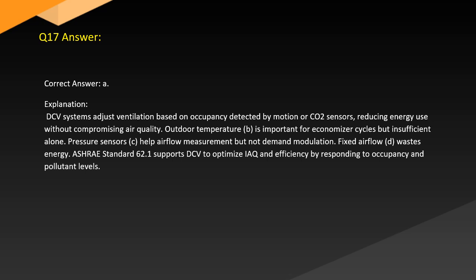Answer. Correct answer: A. Explanation: DCV systems adjust ventilation based on occupancy detected by motion or CO2 sensors, reducing energy use without compromising air quality. Outdoor temperature, B, is important for economizer cycles but insufficient alone. Pressure sensors, C, help airflow measurement but not demand modulation. Fixed airflow, D, wastes energy. ASHRAE Standard 62.1 supports DCV to optimize IAQ and energy efficiency by responding to occupancy and pollutant levels.